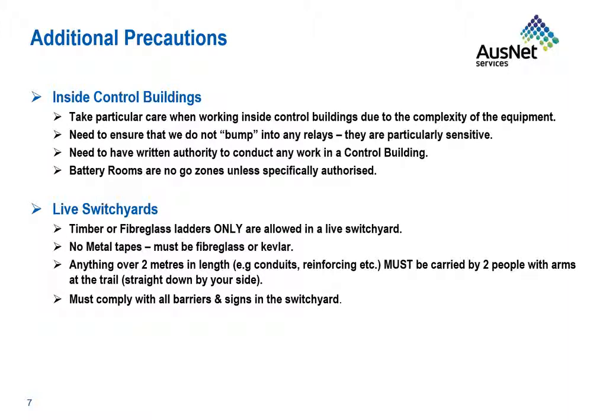Inside control buildings. Take particular care when working inside control buildings due to the complexity of the equipment. Ensure that we do not bump into any relays, they are particularly sensitive. Have written authority to conduct any work in a control building. Battery rooms are no-go zones unless specifically authorised. Live switchyards. Timber or fiberglass ladders only are allowed in a live switchyard. No metal tapes, must be fiberglass or Kevlar. Anything over 2 meters in length, for example conduits and reinforcing, must be carried by 2 people with arms at the trail, straight down by your side. Must comply with all barriers and signs in the switchyard.